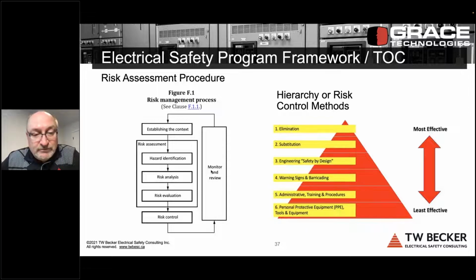This is a great flow chart, it's simple, but even this has not been referred to by employers in Annex F. Your electrical safety program should include a formal qualitative risk assessment procedure, with an electrical hazard risk assessment matrix and a work task-based risk register table. What we're doing is trying to validate these controls—the ones that as an employer we can implement.